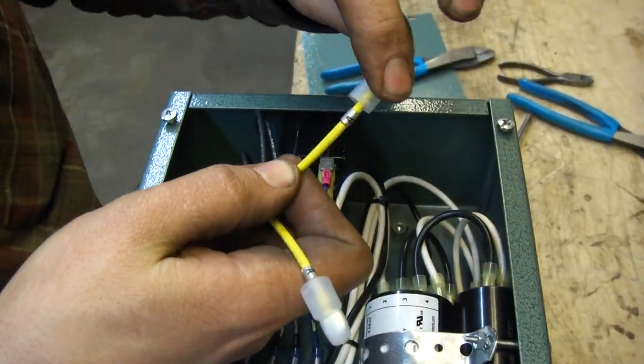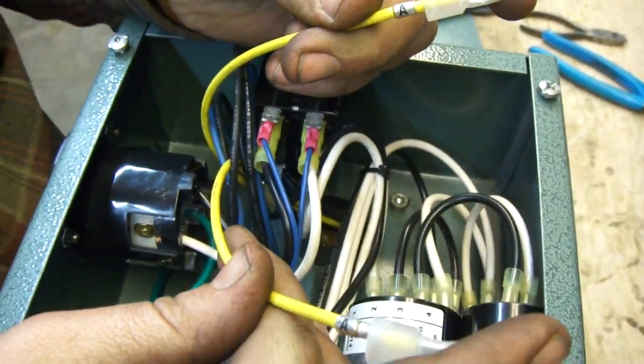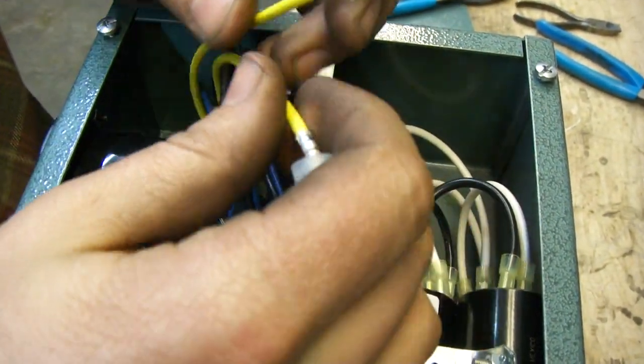Two labels, A and A1. These need to be capped off independently. If they're connected together, the motor won't run.